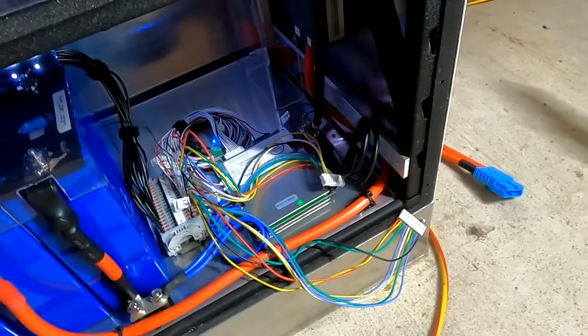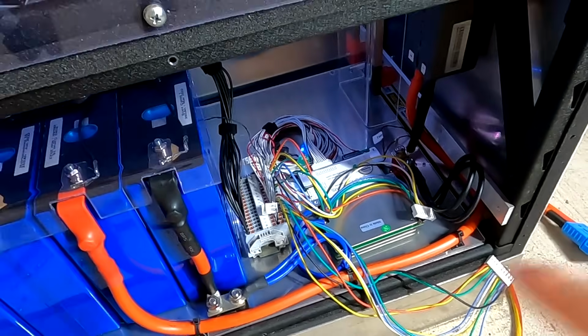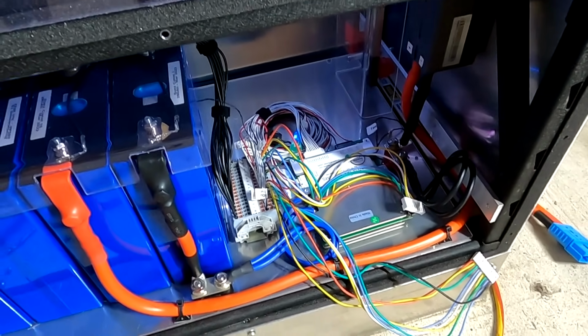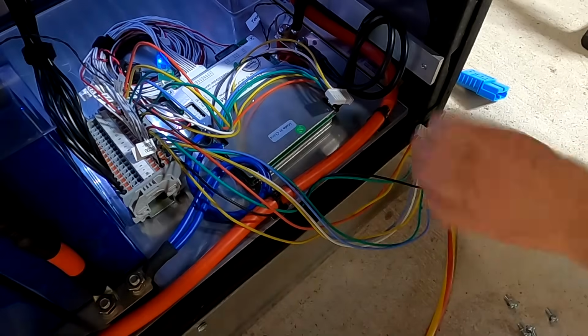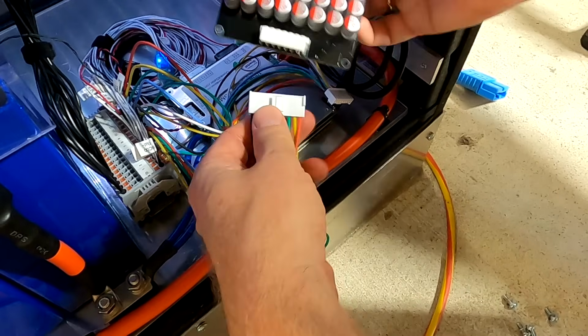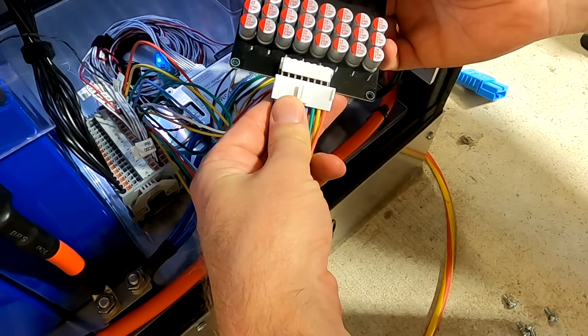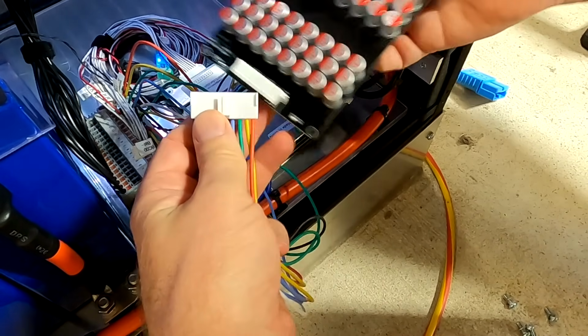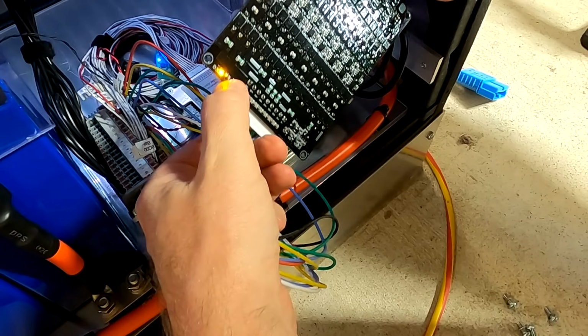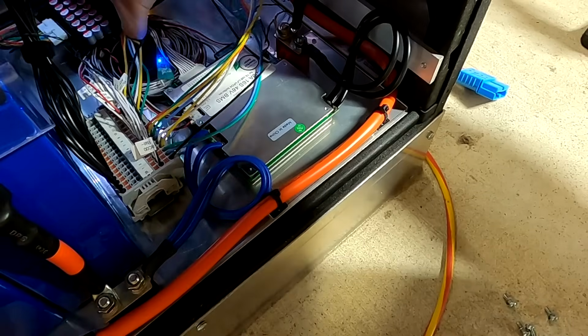So we connected the balance cable harness to our terminal block in the bottom shelf battery, checked all the voltages. Okay, we now connect the active balancer here in the bottom shelf. No, that's the wrong one. Light is on, balancer is working. Okay, we put them on the aluminium shelf. I would say let's leave this running here for the next half an hour.